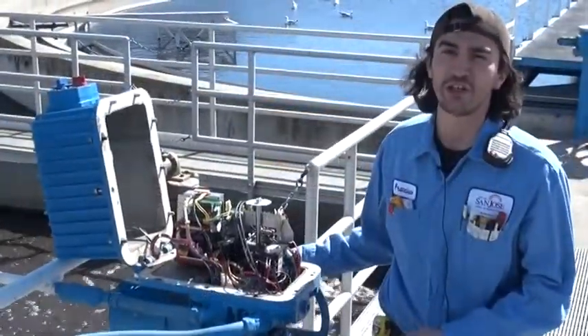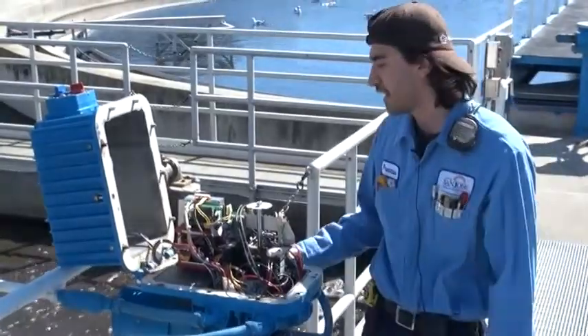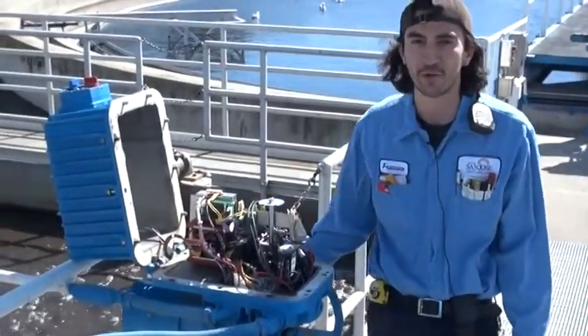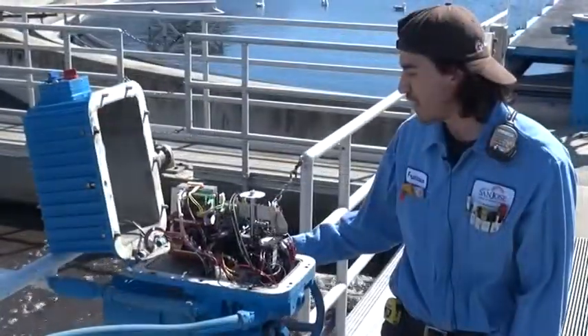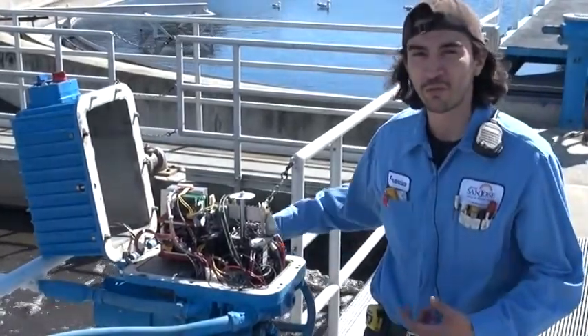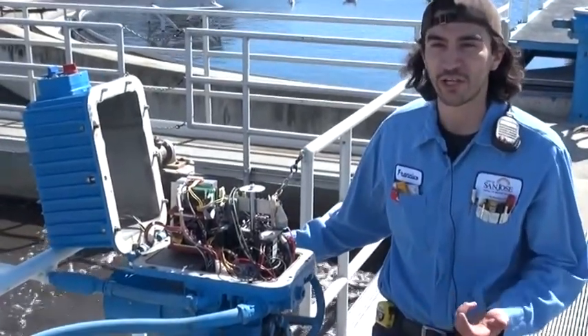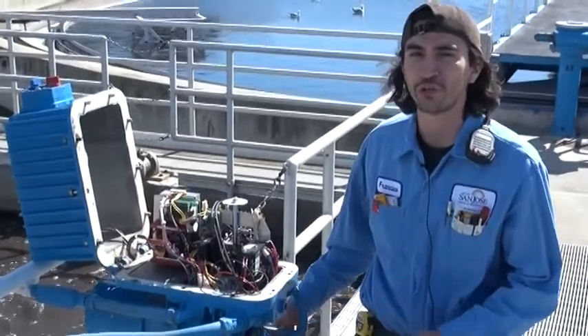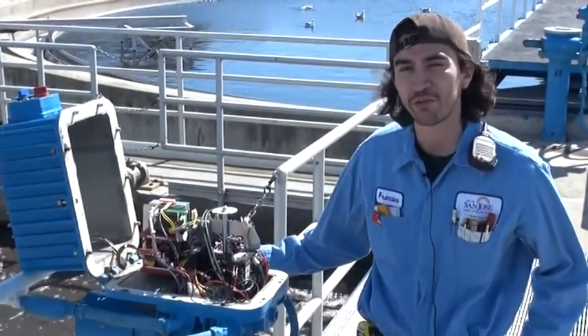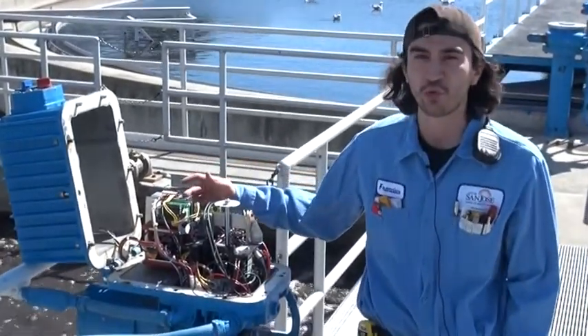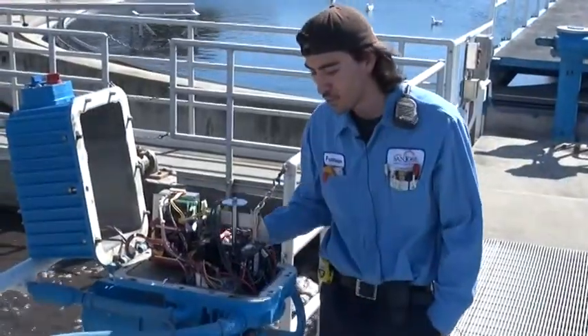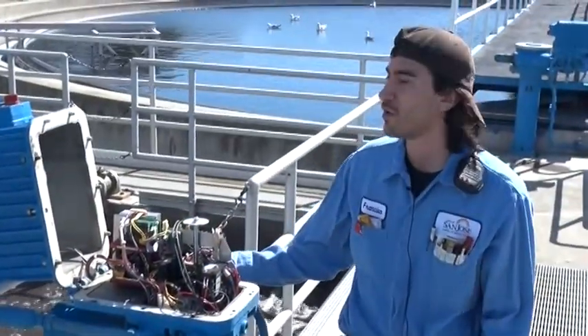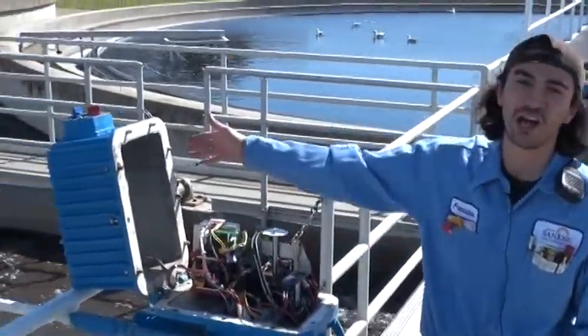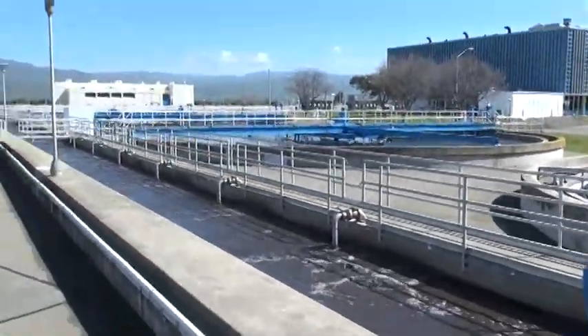Upon installation of these valves, some of the main things we've got to do is a full-blown calibration on them. Part of doing that is we'll hand-wheel open and close to set our limits, and then we simulate our 4 to 20 signal coming from the DCS using a simulator, and calibrate the 4 to 20 here. That's one of the routine things we do here on the plant, and as you can see we have lots of these on site, so it keeps us pretty busy.